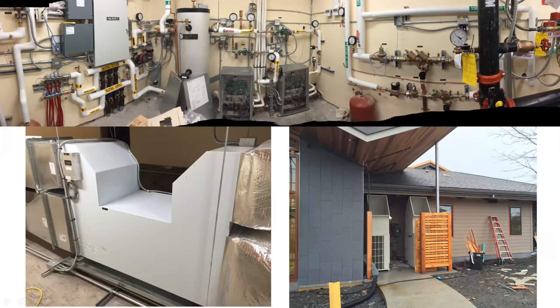Down to the lower right, we can see 2 VRF units. We've got a little hood on the top to kick the air out, because it was blasting at this underpin, and up there icicles were a concern, so we had to route around these icicles that would form.